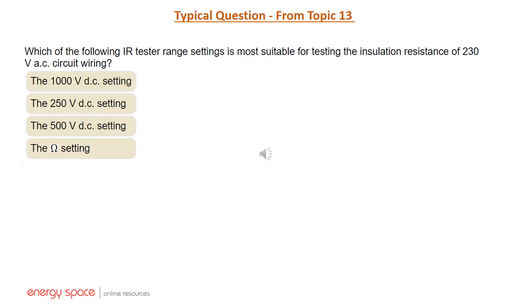I know I've mentioned this a number of times: an IR tester, which is an insulation tester, is meant to test the insulation resistance of a particular cable. So it's trying to punch a small amount of current through the plastic insulation of a cable to another cable - from, let's say, an active conductor to the earth conductor.